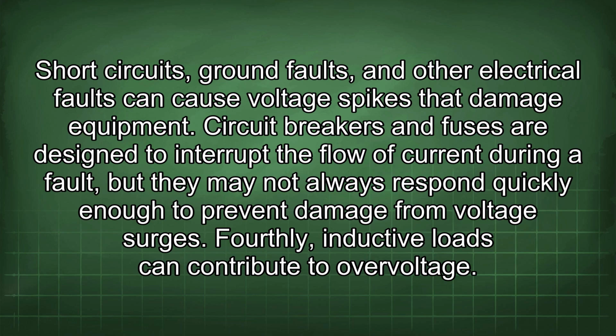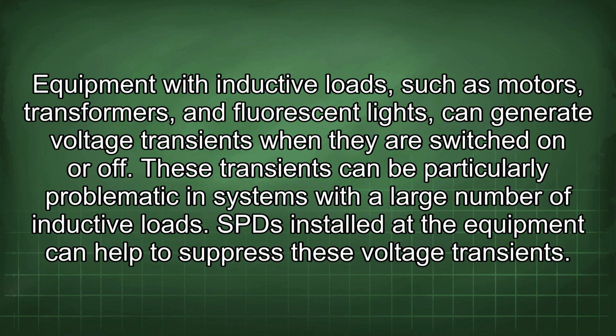Fourthly, inductive loads can contribute to overvoltage. Equipment with inductive loads, such as motors, transformers, and fluorescent lights, can generate voltage transients when they are switched on or off. These transients can be particularly problematic in systems with a large number of inductive loads. An SPD installed at the equipment can help to suppress these voltage transients.